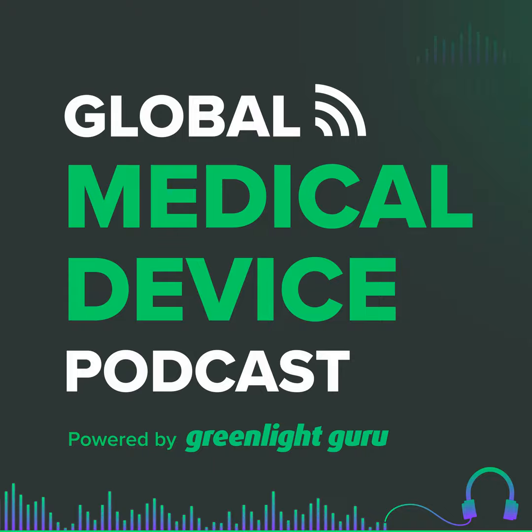So that's one of the two reasons why I make that recommendation. In other words, sort of a sanity check. Say, okay, Mr. and Mrs. FDA reviewers, here's our device. This is what it does. This is how it works and so on. For all of the following reasons, it is a non-significant risk device. And then FDA will say, great, that sounds logical to us.